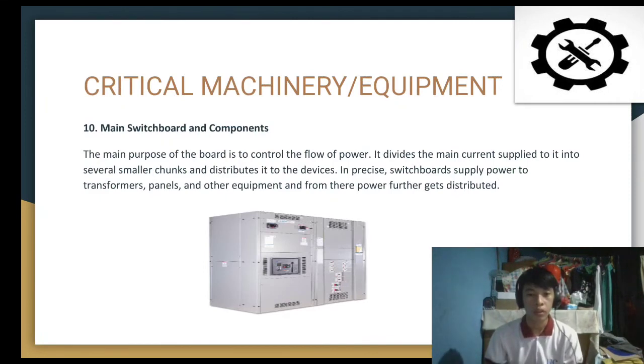The last one, the tenth critical machinery or equipment, is the main switchboard and components. The main purpose of the board is to control the flow of power. It divides the main current supplied to it into several smaller chunks and distributes it to the devices. In precise terms, the switchboard supplies power to transformers, panels, and other equipment, and from there power further gets distributed. A switchboard is a component of an electrical distribution system which divides an electrical power feed into branch circuits while providing a protective circuit breaker or fuse for each circuit in a common enclosure.